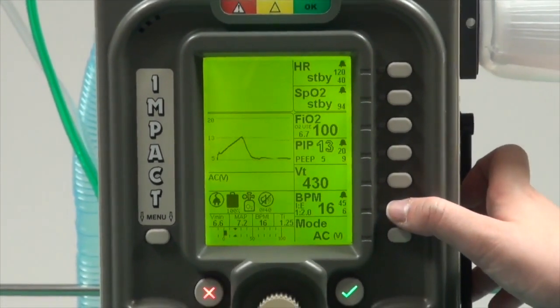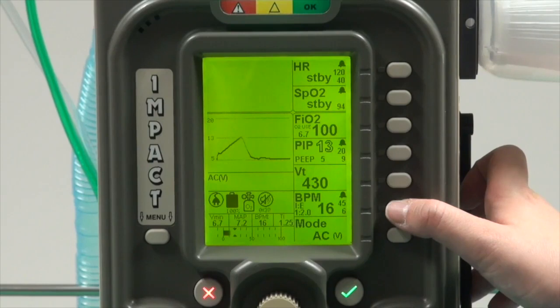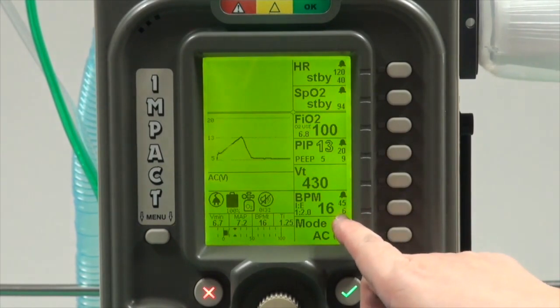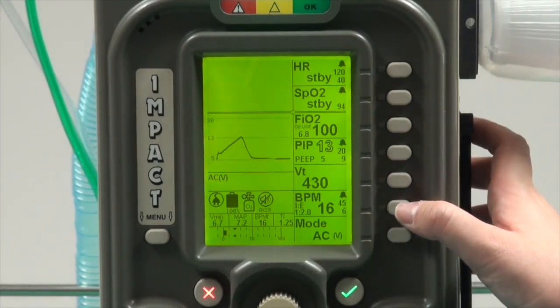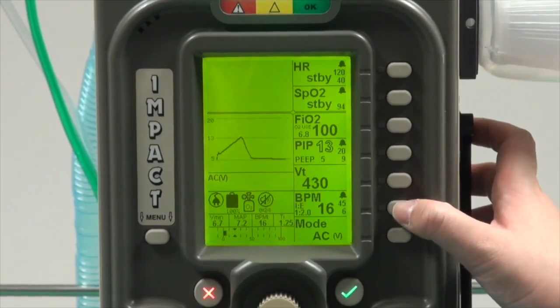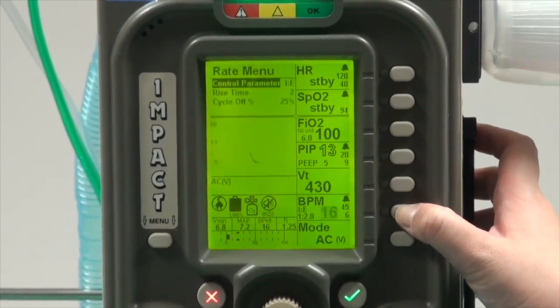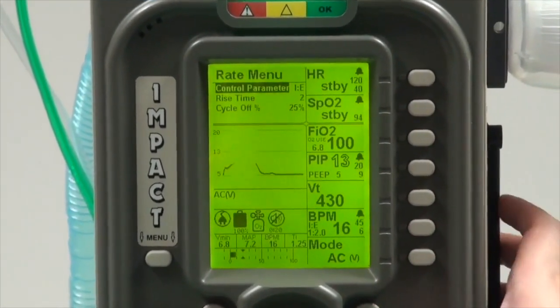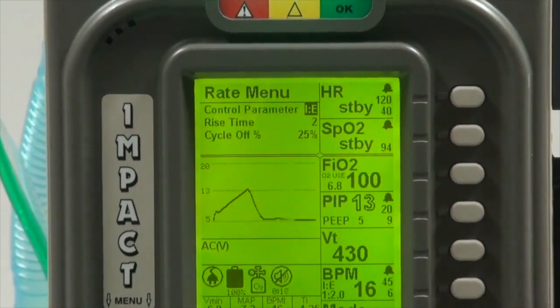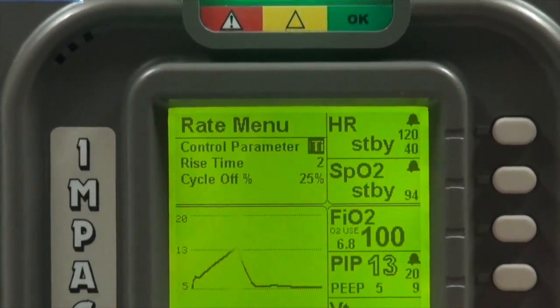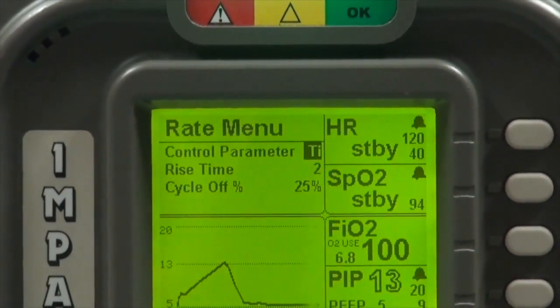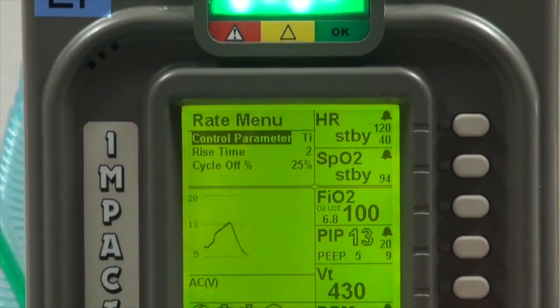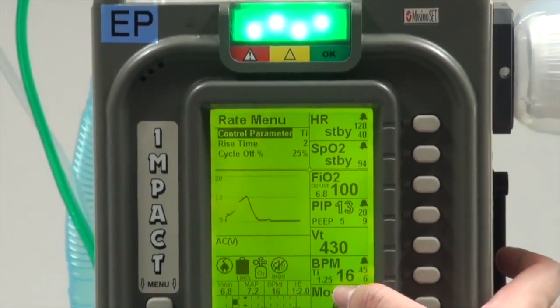We also have the I to E ratio and alarm limits for high and low respiratory rate. Alarm limits are denoted by the alarm bell above the smaller numbers over here. If you want to change from I to E ratio to inspiratory time, you can press and hold this button. The rate menu comes up. Confirm that this is what you want to change, and then confirm the change. Notice how it changes to TI over here.